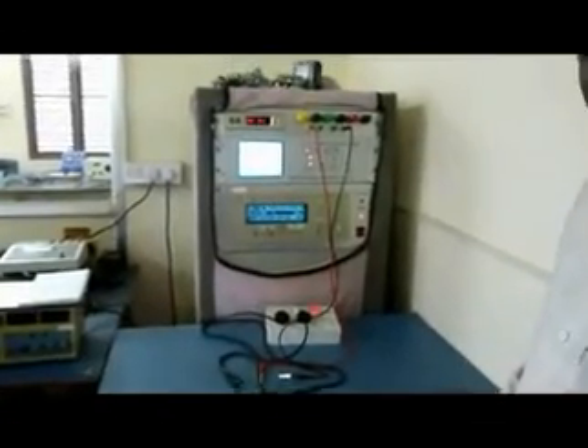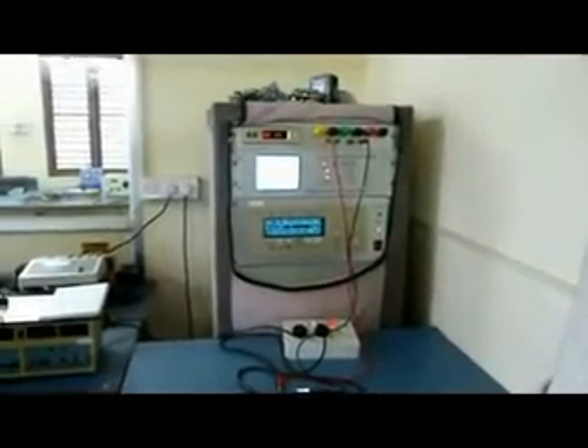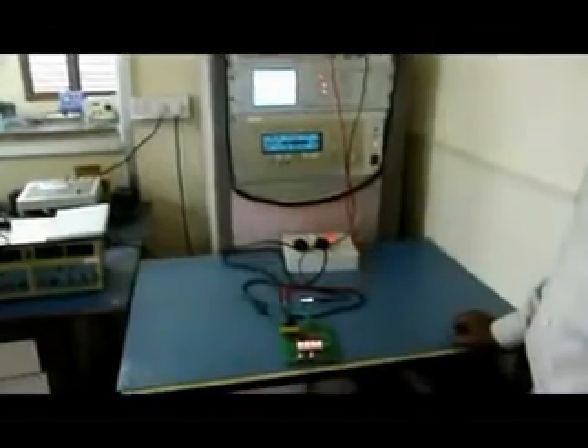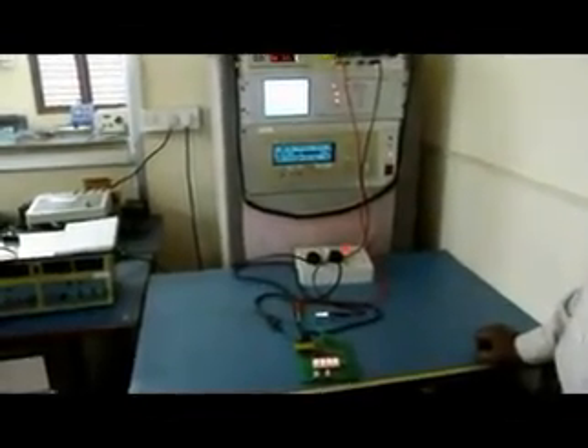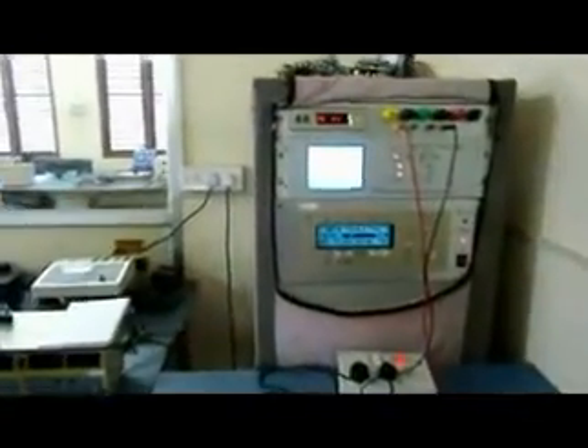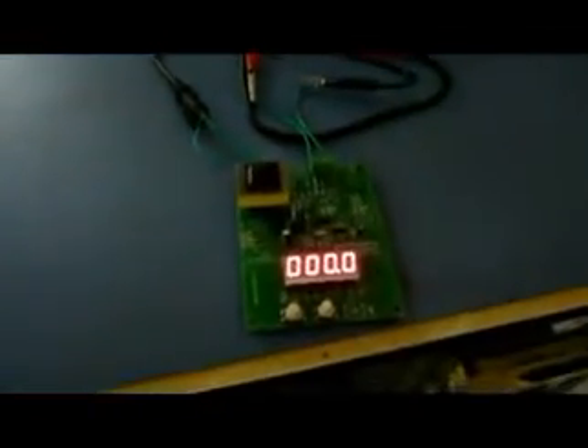We are at a test facility that does calibration and testing, and we have our DPM digital panel meter board connected to a reference source and a reference meter, and we are going to apply a series of inputs to it, and we are going to see what outputs we are getting on the display. The display on the reference meter is going to be very small. Right now, the voltage input on the reference is showing 0.0, and that is exactly what the DPM is showing at this moment.